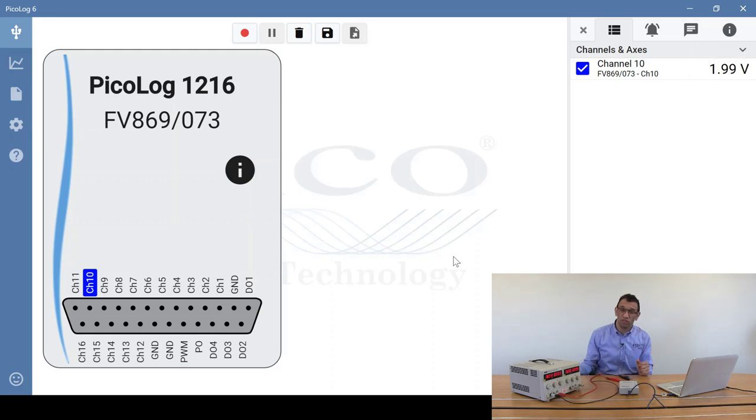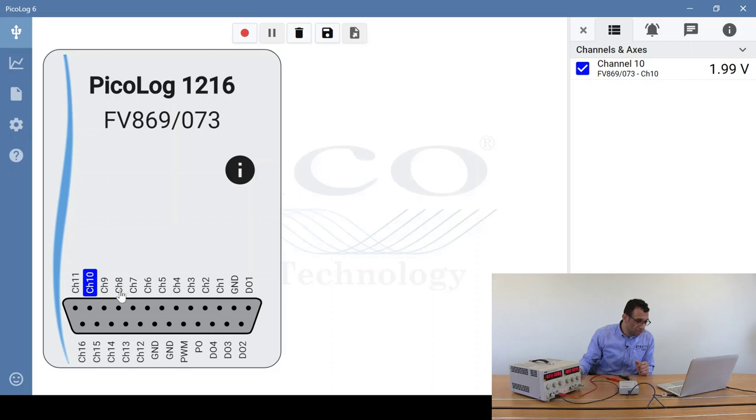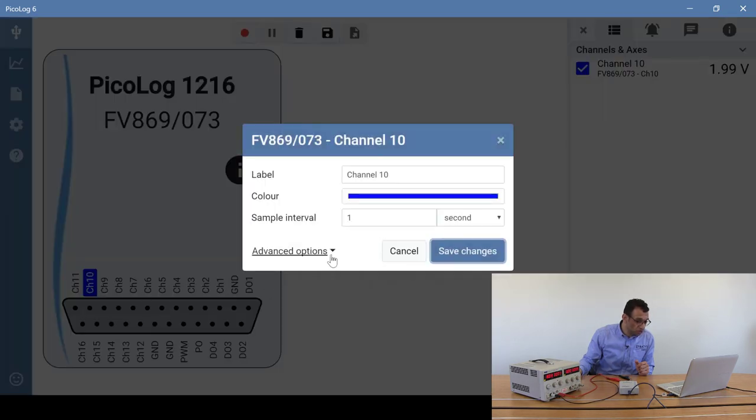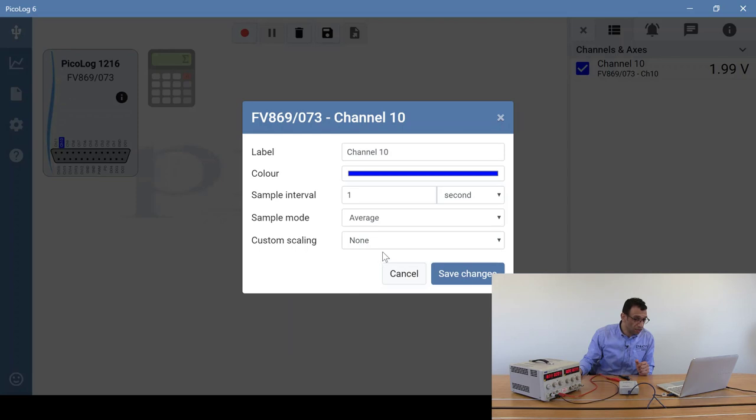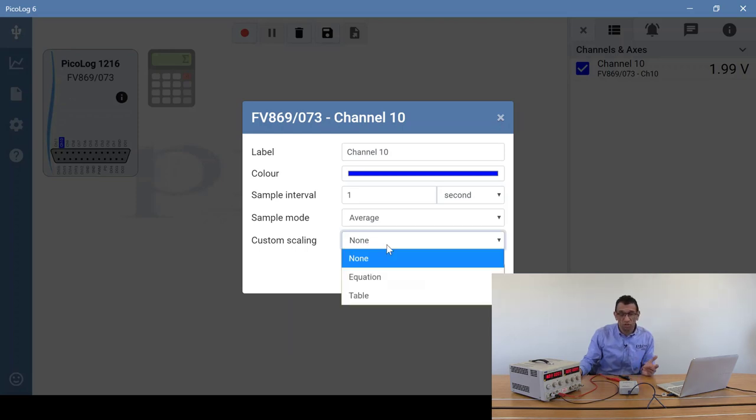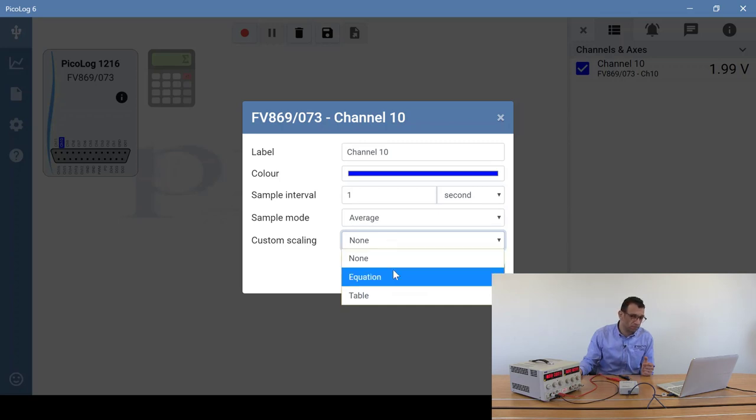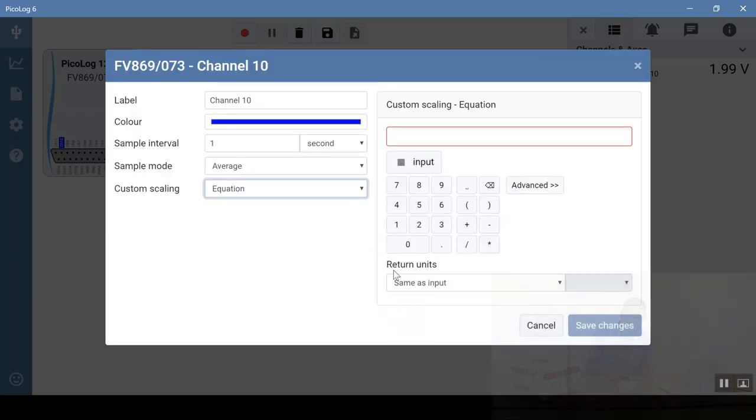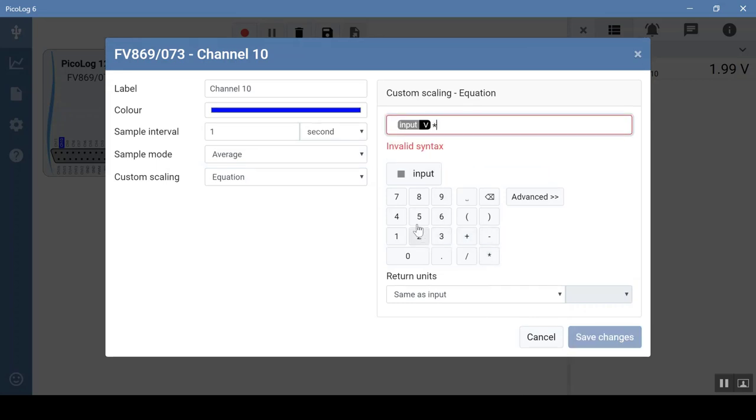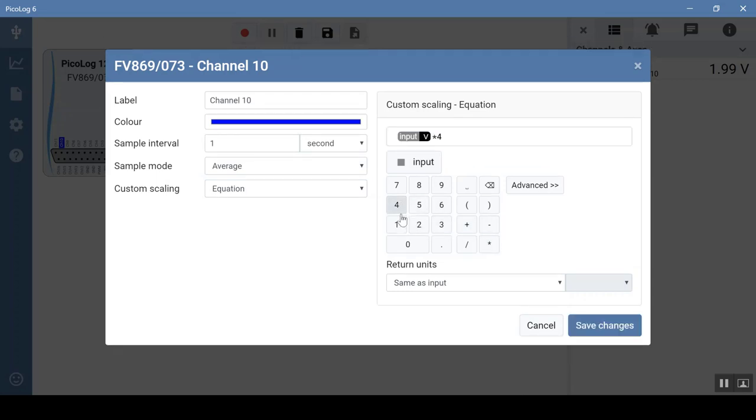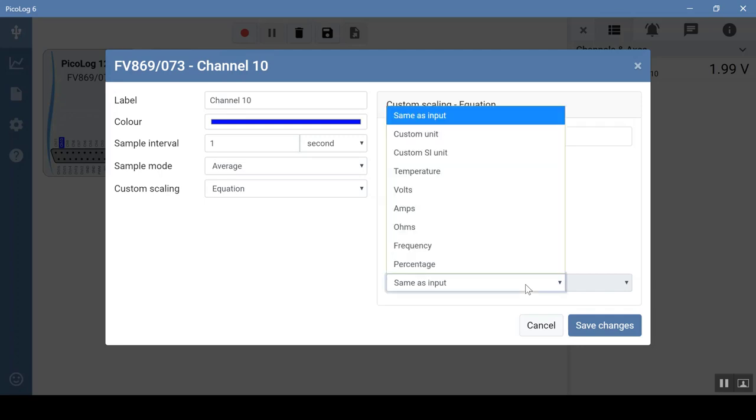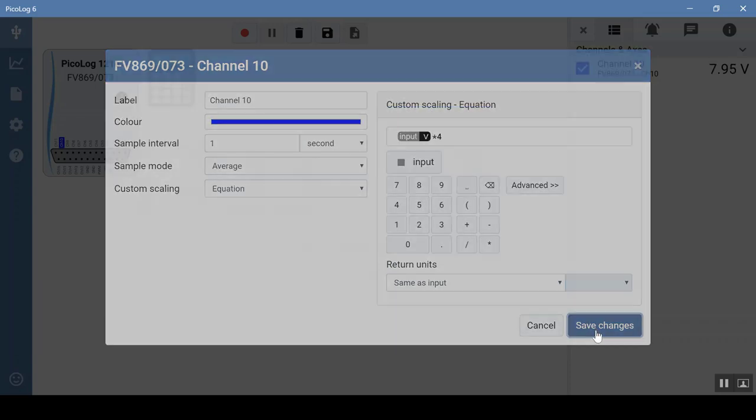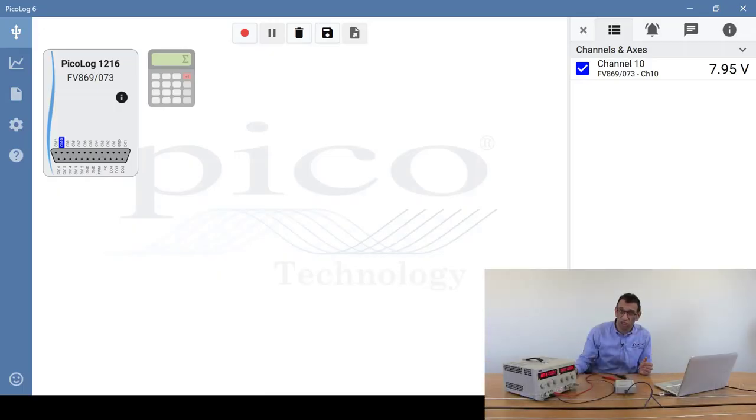Now we need to do some custom scaling. I'll go back to channel 10, click on it, go to advanced options, and select custom scaling. There's two types of scaling: equation and table. We'll start off with equation. So I'll type input multiplied by 4, and the return units will leave as is because it's still measuring voltage, but you can vary the return units if you require. Click on save changes, and as you can see, the voltage has changed accordingly.